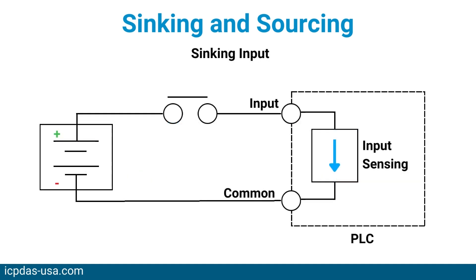The device receiving the signal does not provide power. It acts as a resistive load and must be connected to the device that sources its output signal, or to a sinking output with a loop power supply in the circuit.